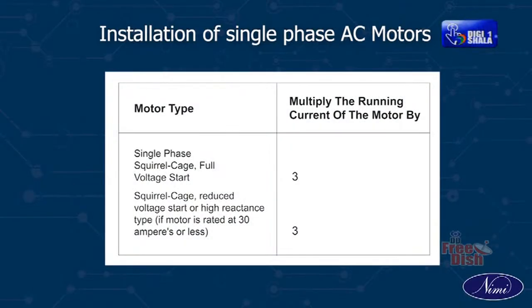Calculating fuse ratings of motors. Motor type: multiply the running current of the motor by 3 for single phase squirrel cage full voltage start, and by 3 for squirrel cage reduced voltage start or high reactance type if the motor is rated at 30 ampere or less.